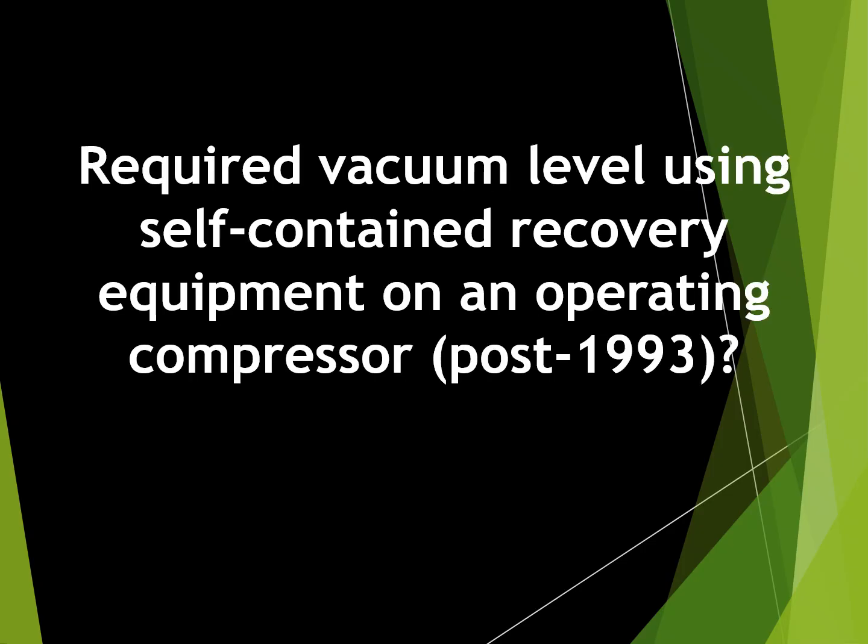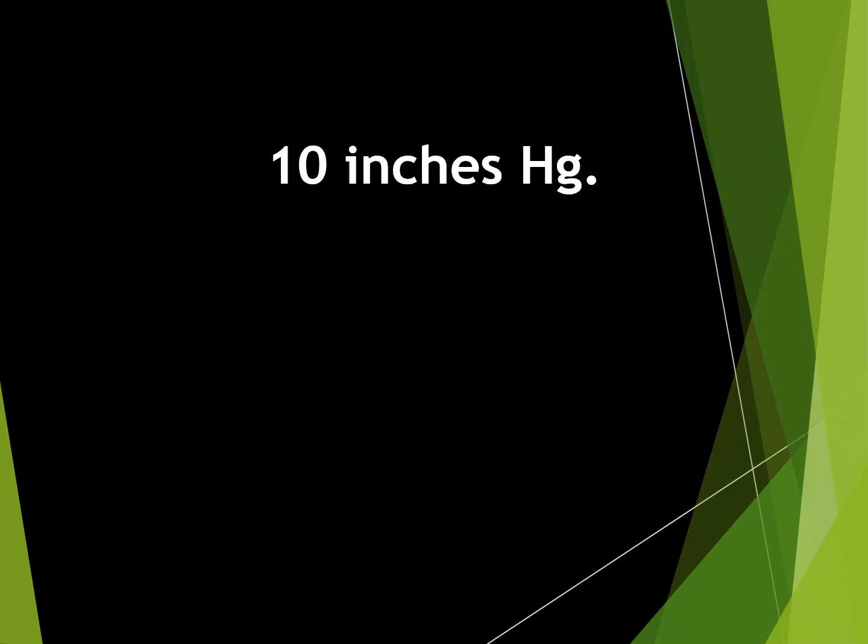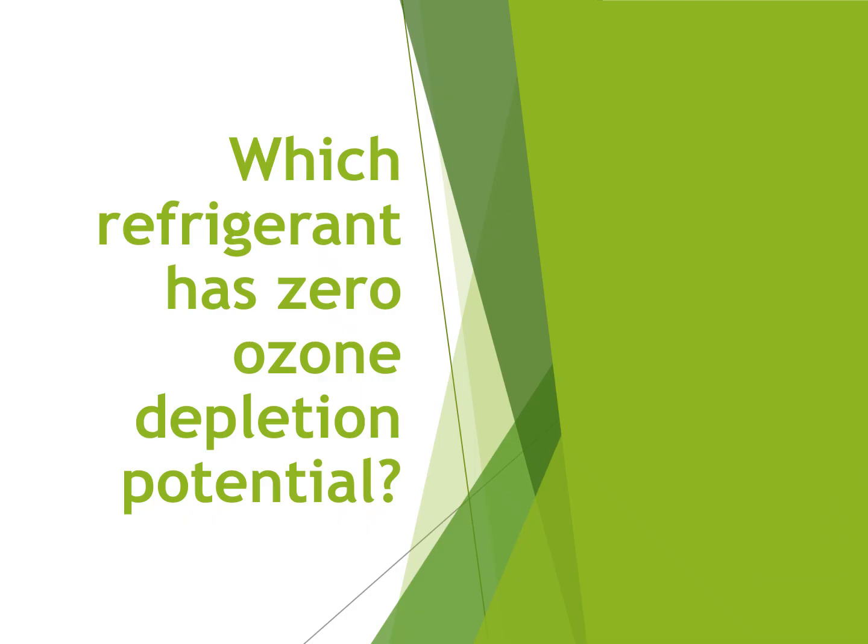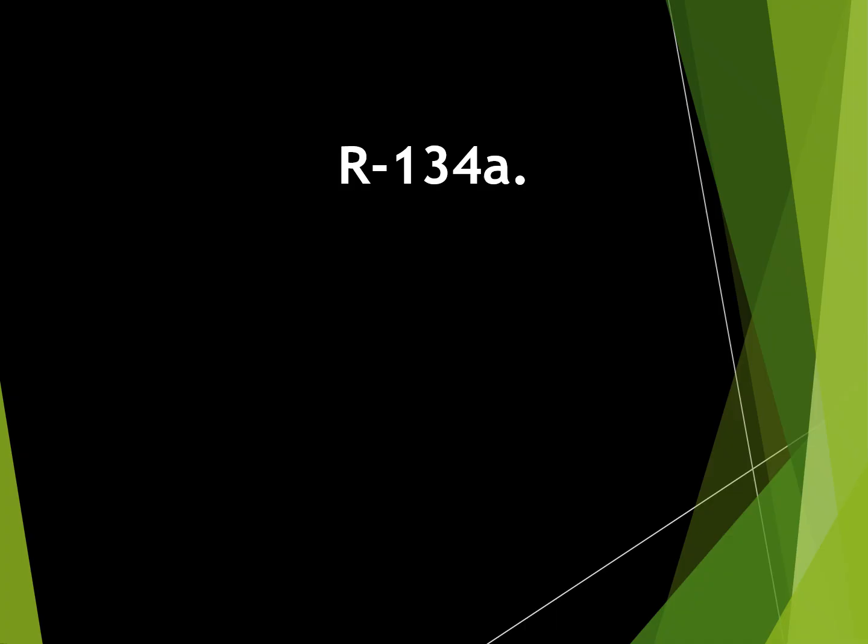A3. Required vacuum level using self-contained recovery equipment on an operating compressor, post 1993. 10 inches Hg. Which refrigerant has zero ozone depletion potential? R134A.